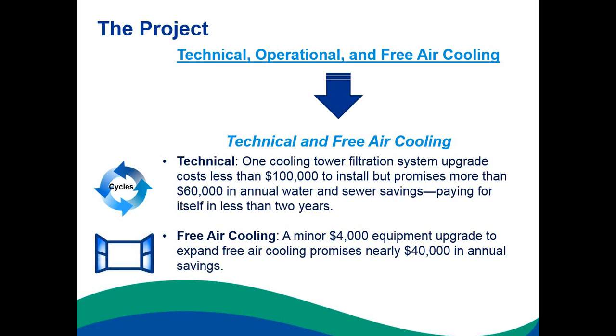Working through all three approaches, we found—not surprisingly—that the technical and free air cooling approaches showed the best results. For example, AT&T found that one cooling tower filtration system upgrade cost less than $100,000 to install, returned $60,000 in annual water and sewer savings, and paid for itself in less than two years.